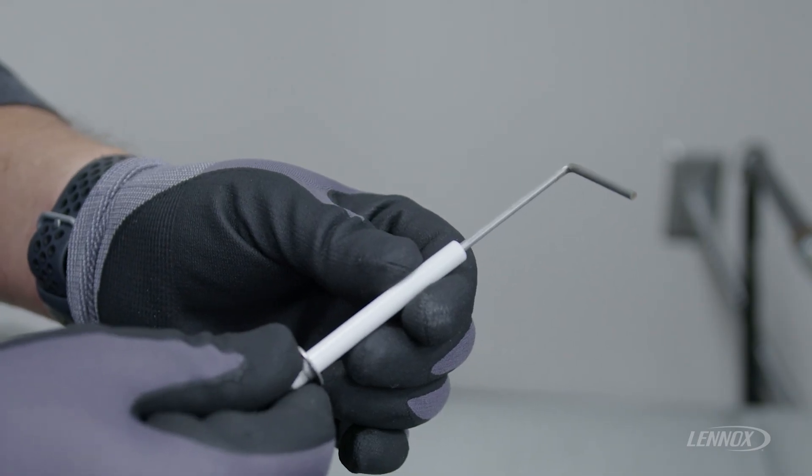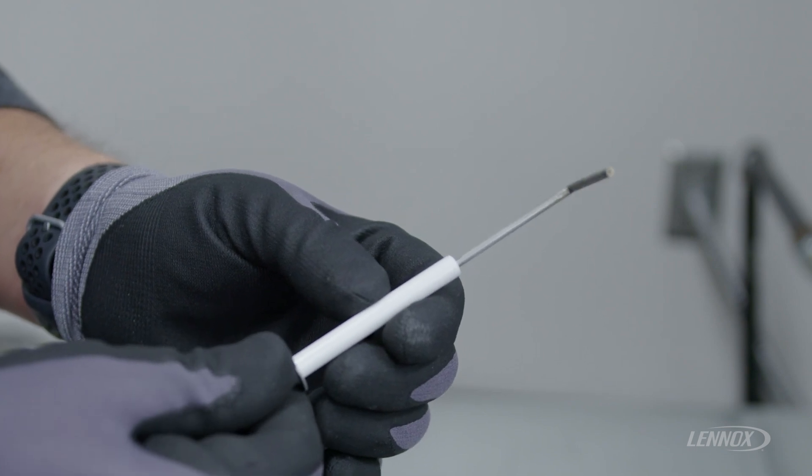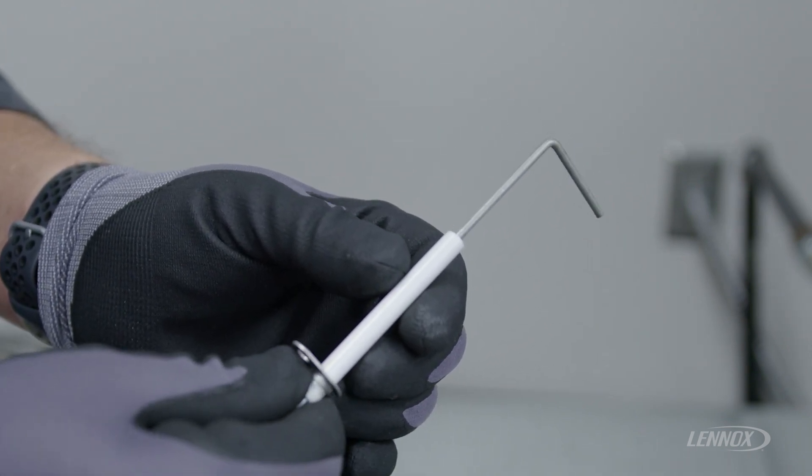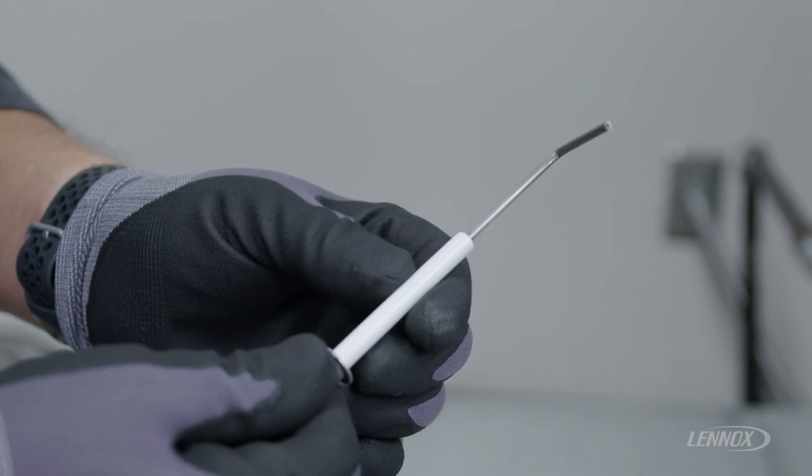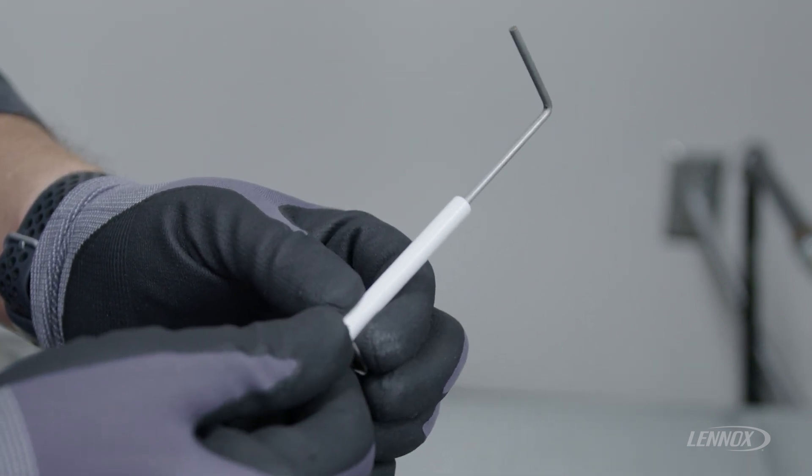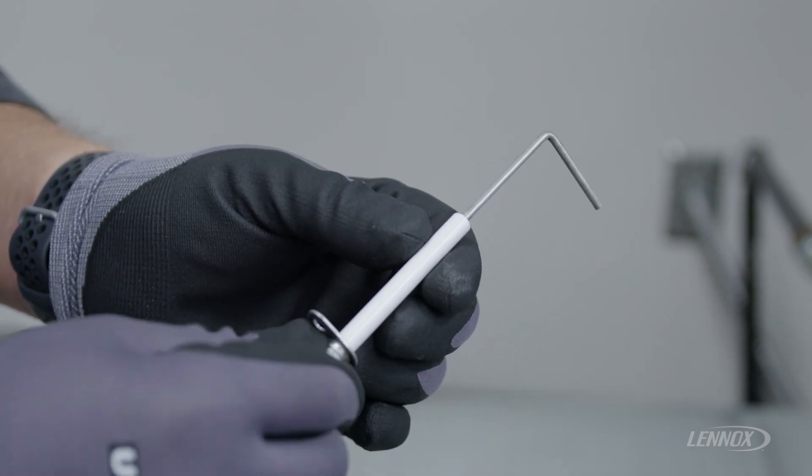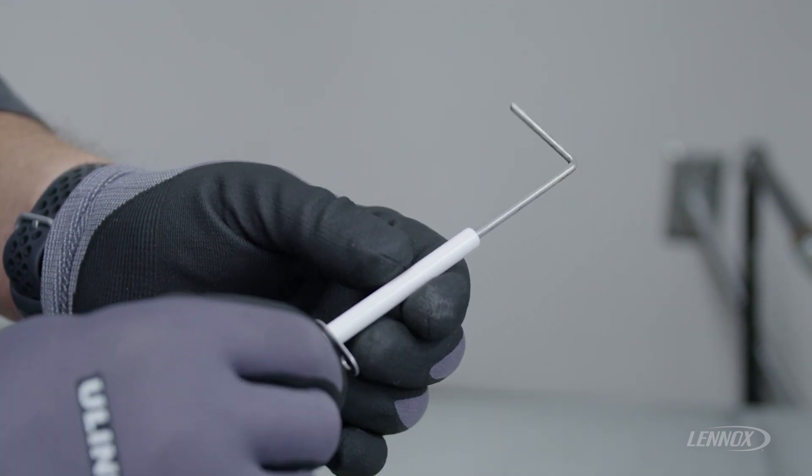Once you have the flame sensor removed, there's another process we have to verify involving the porcelain insulator that is located at the base of the flame sensor. We've got to inspect this porcelain base to make sure there's no cracks, breaks, or interruptions that might delay the process of the flame rectification.